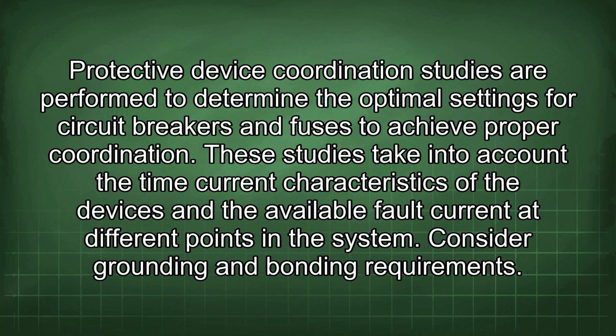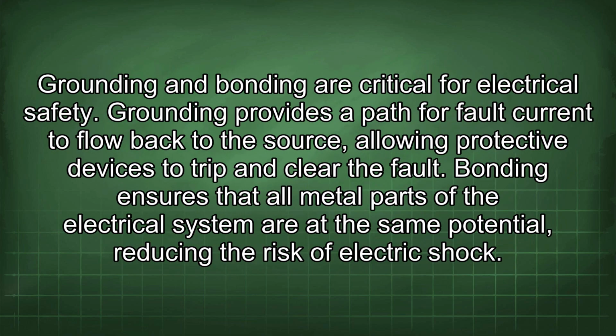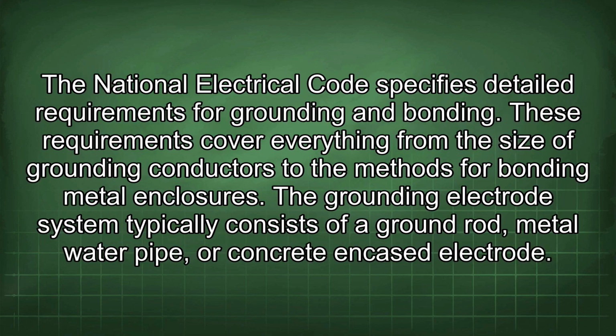Consider grounding and bonding requirements. Grounding and bonding are critical for electrical safety. Grounding provides a path for fault current to flow back to the source, allowing protective devices to trip and clear the fault. Bonding ensures that all metal parts of the electrical system are at the same potential, reducing the risk of electric shock. The National Electrical Code specifies detailed requirements for grounding and bonding. These requirements cover everything from the size of grounding conductors to the methods for bonding metal enclosures.